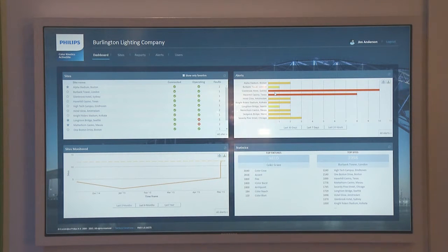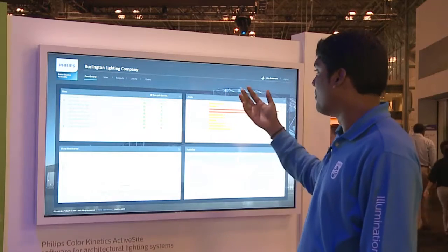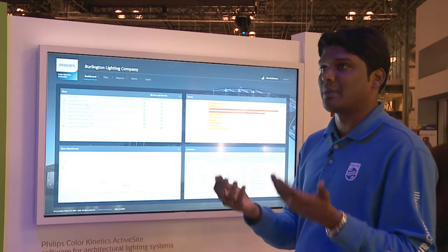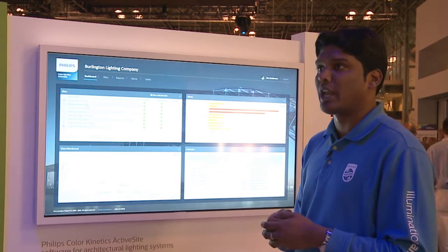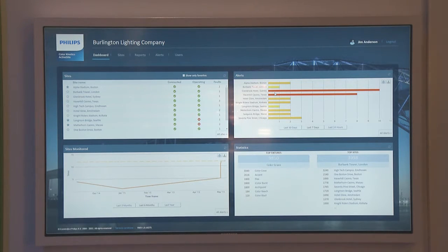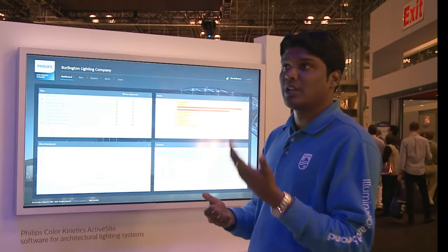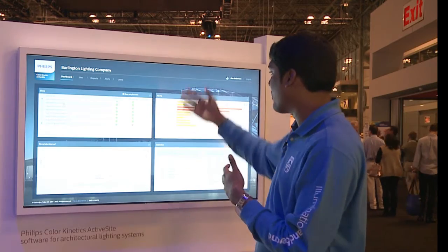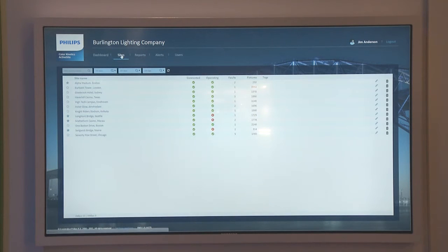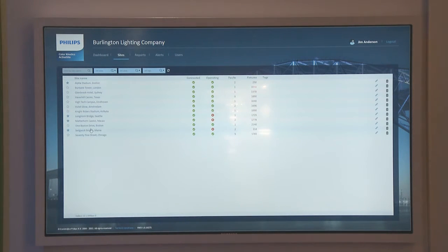You come in and see all the email alerts from that installation. So if a fixture is not working, if a power supply has gone bad, if a controller stopped working — all of this is recorded in the software. If something goes bad, you immediately get an email alert. You don't even have to come into the software if you haven't received an alert. If you do get an alert and want more analysis, you jump into the software and look at what's going on. There are a lot of statistics here — the number of connected light points, the number of sites you've monitored over time, and their status over time.